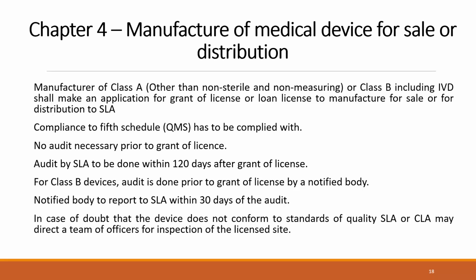Also, for Class B devices, an audit is done prior to the grant of the license by a notified body. The notified body reports to the state licensing authority within 30 days of the audit. If they have asked any further queries, they have to be answered within this duration. In case of doubt that the device does not conform to standards of quality, both the state and central licensing authorities may direct a team of officers to inspect the licensed site, based on the documents and the device functionalities. If they still have queries, they can send a team to inspect the site as well. This is all mentioned under sale or distribution.